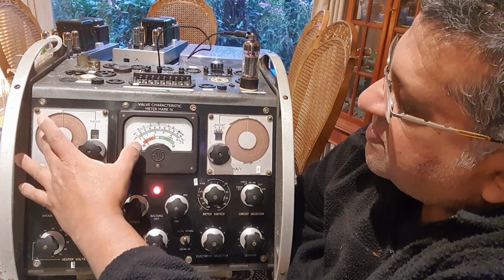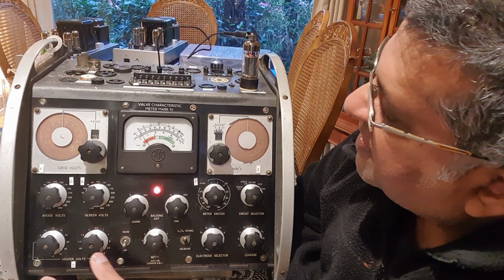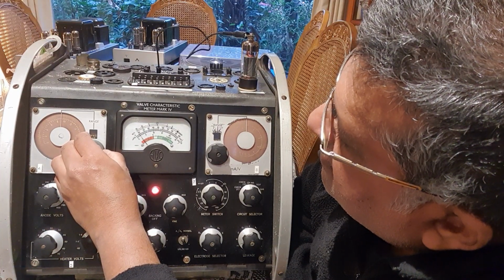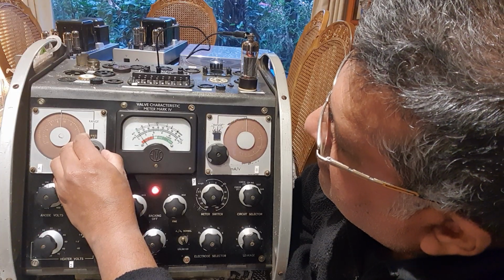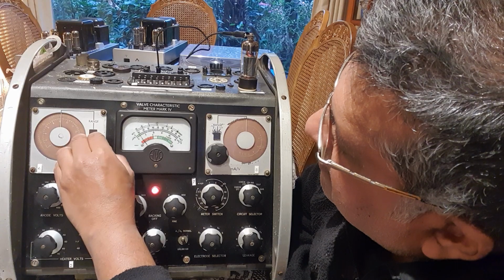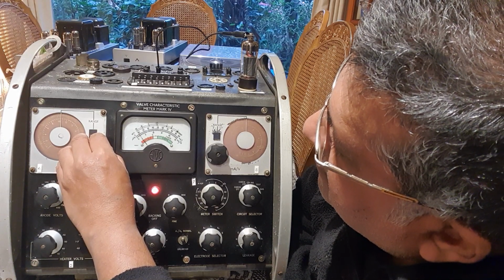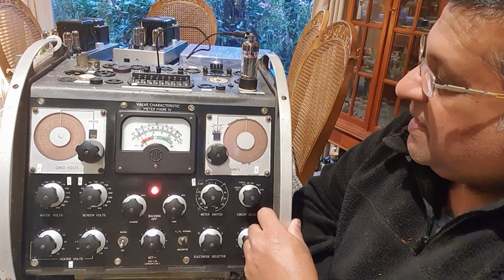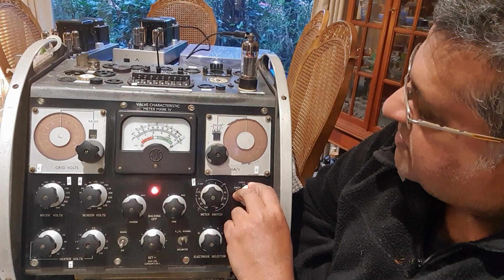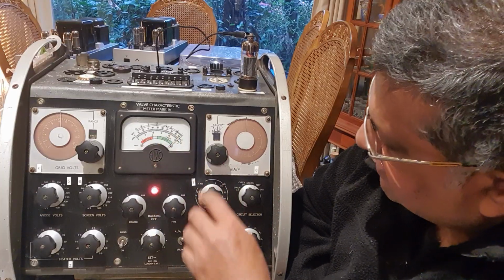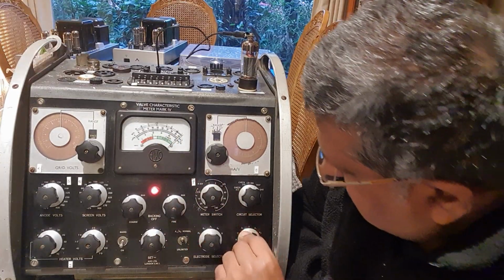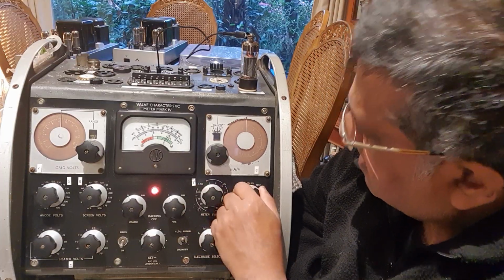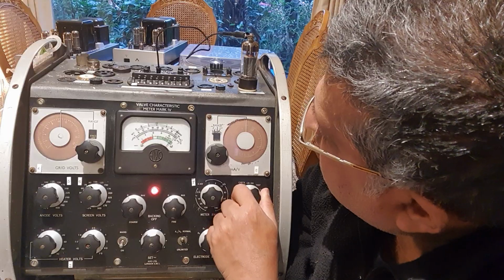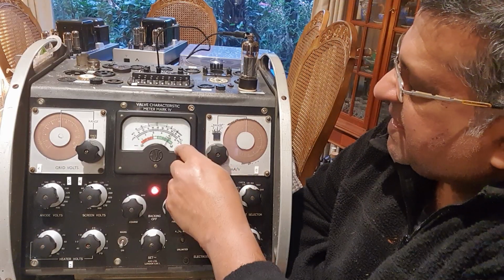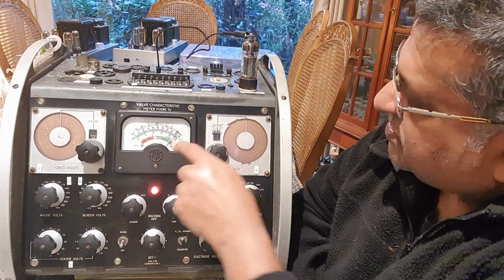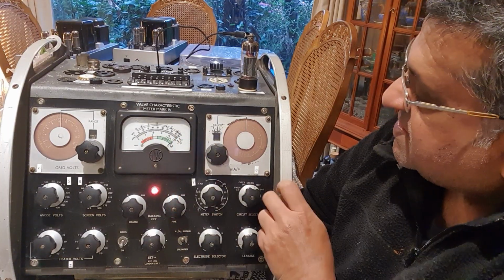These are on hundreds. This is on 7.7, and right, yeah, 7.7. Sorry, I've got the wrong setting. 7.5 and 2. Yeah, that's where I should be. So basically we are good to go ahead for the test. When we go for the test and the meter has deflected above, I'm just going to double check. So the meter has deflected into the 100. I've just switched off.